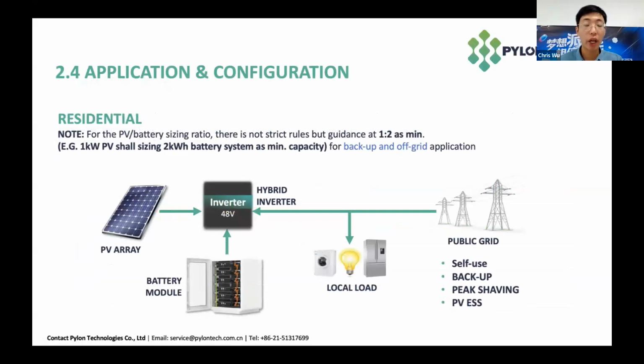So for our low voltage battery, here is a diagram that shows the application and also the configuration. This is a hybrid system, and the customer can connect it to the public grid, or he can also do an off-grid system. It's both fine. The customer will purchase a PV array, a hybrid inverter, as well as our battery modules. And for the sizing ratio, we usually recommend the customer to have a 1:2 ratio for the system. For example, if the customer has 1 kilowatt of PV, he should purchase a 2 kilowatt-hour battery system for the backup or off-grid application.